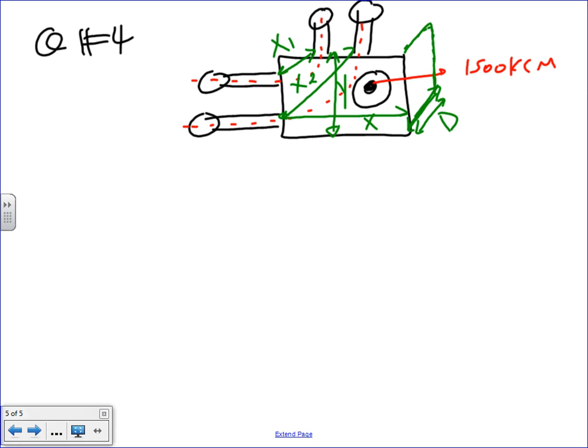Any question, guys, before we start that one? This is not as ugly as the one that I gave you guys. From the get-go, do I have any straight pulls? No straight pulls. All of them are angle pulls. Do I have a U-pull? No U-pulls. Now, if I give you a U-pull, you know how to do it: 6 times the largest conduit engaged, plus all the others.